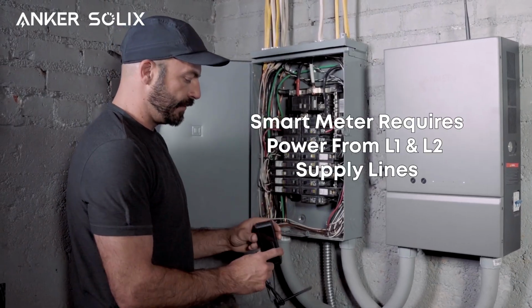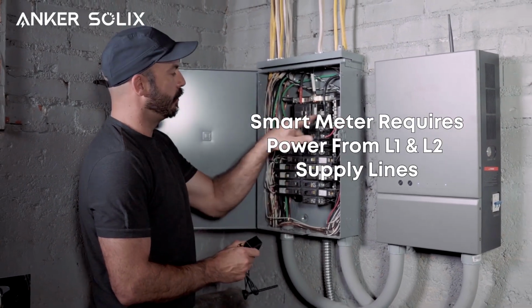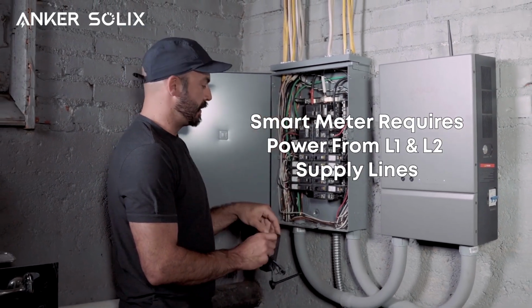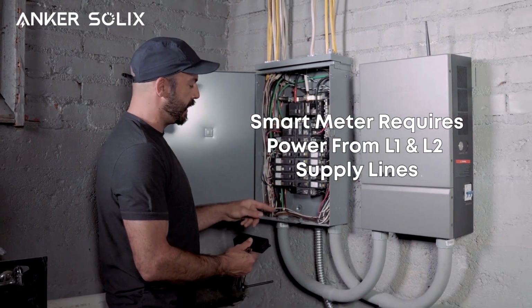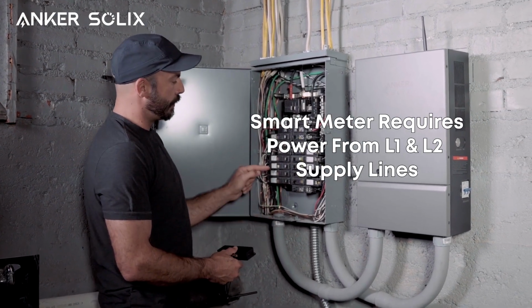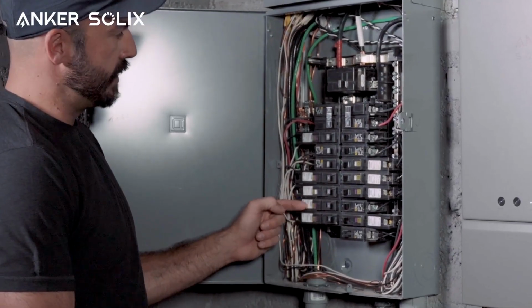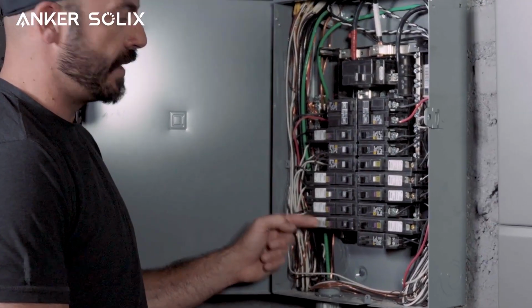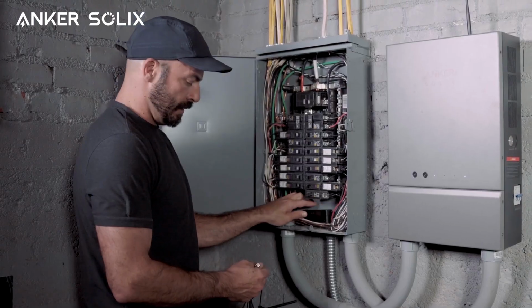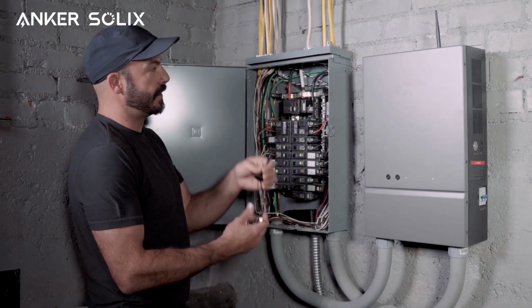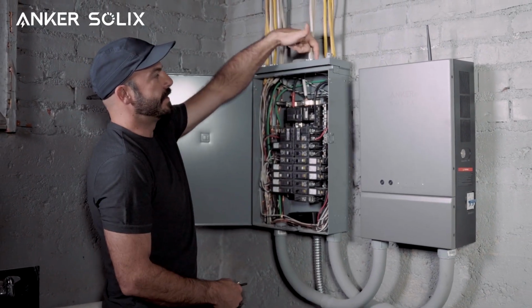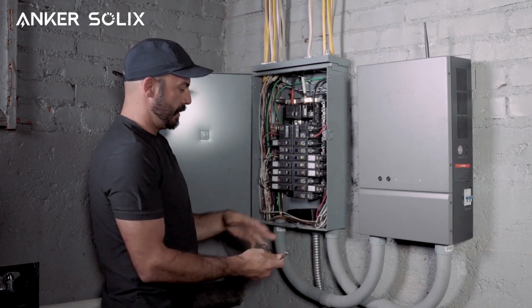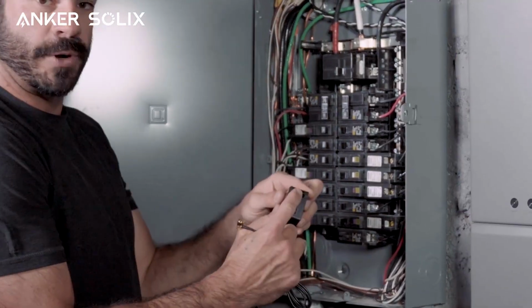The meter itself requires power from both the L1 and L2 supply lines, and we'll do that by splicing in off of two adjacent 15 amp breakers—one from this side, which will be L1, and one from this side, which will be L2. Then we'll mount our antenna on top of the box, making a knockout for the wire to run through, and connect it to this port.